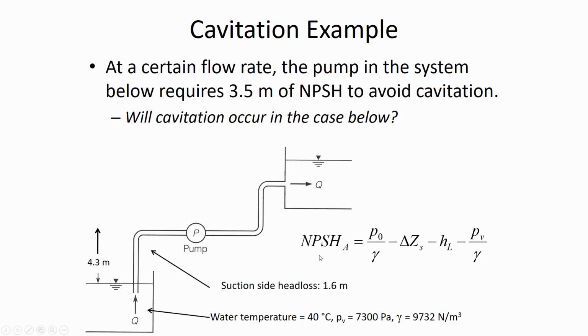And so we're going to do a tally of how much is available. This is just atmospheric conditions, so how much is available starts with the pressure head of the atmosphere, and then we subtract the elevation head, and we subtract the head losses. Just to save time and make the example a little simpler, we're saying those suction side losses are 1.6 meters. In a real-world situation, you'd need to calculate them by knowing the length of the pipe, the f value of the pipe, and the flow rate. In other words, you'd use the Darcy-Weisbach equation. But here they're just given. Let's assume that they solved the Darcy-Weisbach equation, and that's how much head loss you got. And then we also account for the vapor pressure of the water.